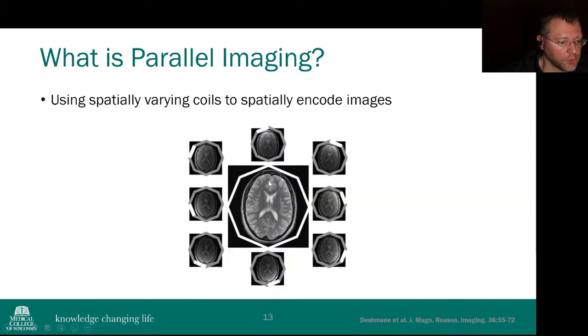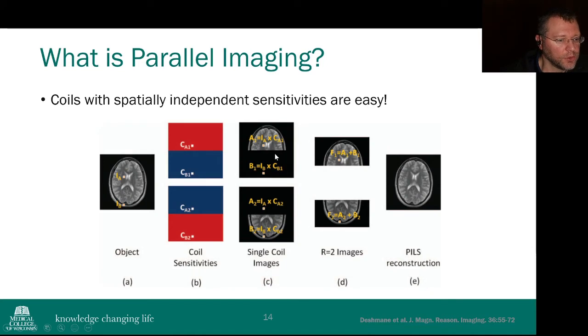So if you have those two coils for the front and the back, and you know their coil sensitivity is going to 0 after you pass that halfway point, you just cut off those 0 points. You have those two, the front image, the back image, and you stitch the two of them together, and you get the output image. As I said, this is what was done initially for this technique called PILS.